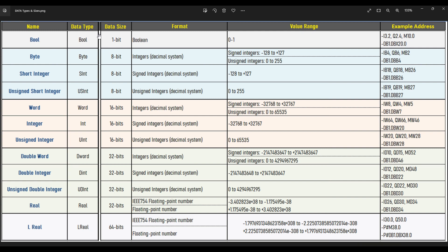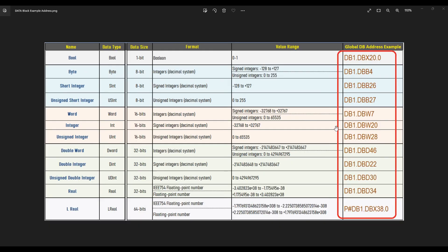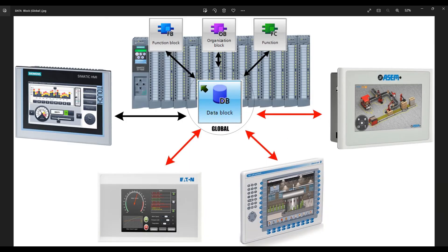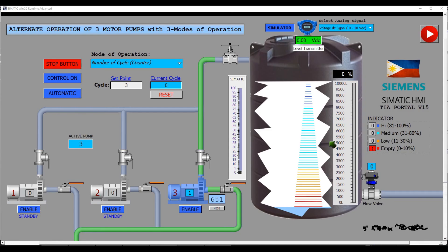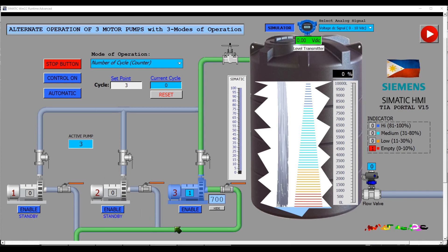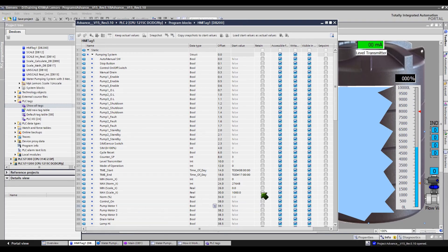These are the common data types in TIA portal using the latest devices like S7-1500: bit, byte, word, integer, double word, double integer, and real — these are the most commonly used data types in PLC programming that you should know. These are examples of data block addresses when accessing data in the CPU. You can use a global data block in different ways: you can access it from a PLC organization block, function, or function block. All of my HMI process tags in this system were established in the global data block.